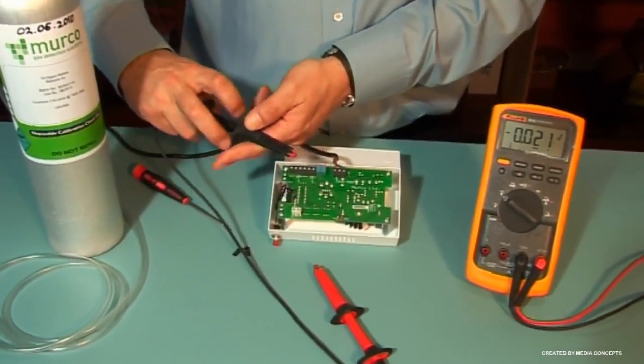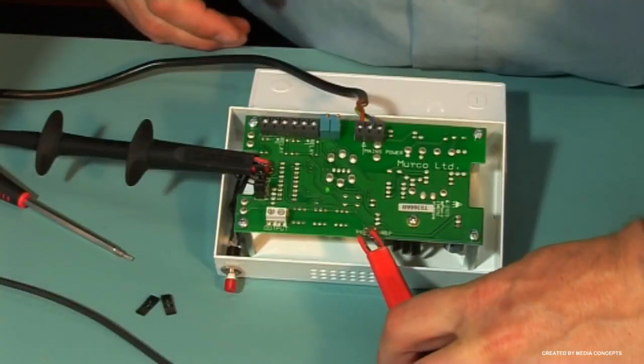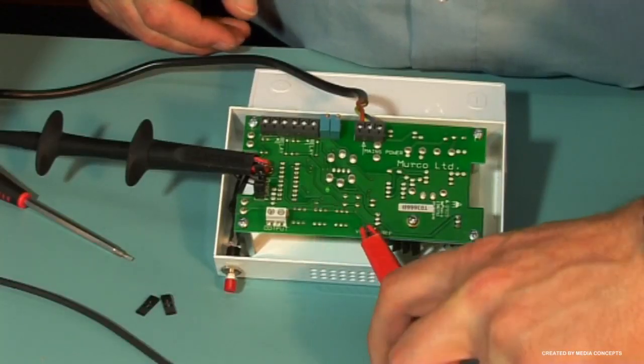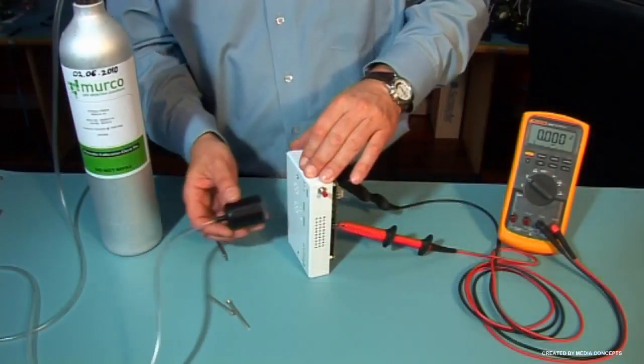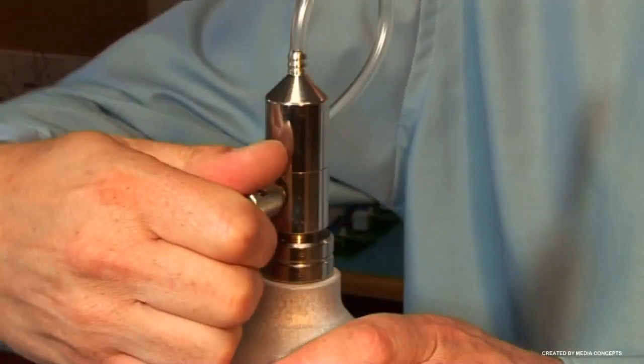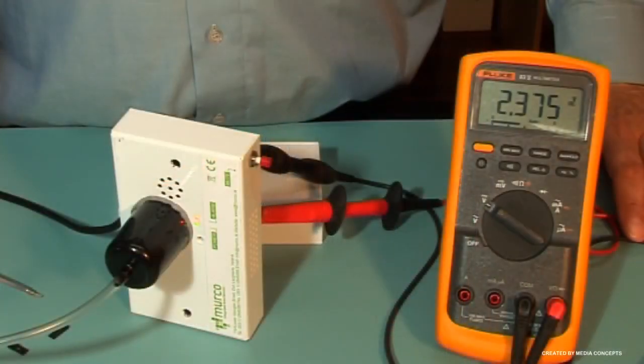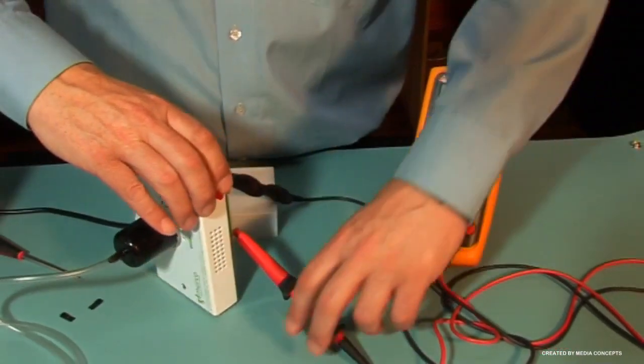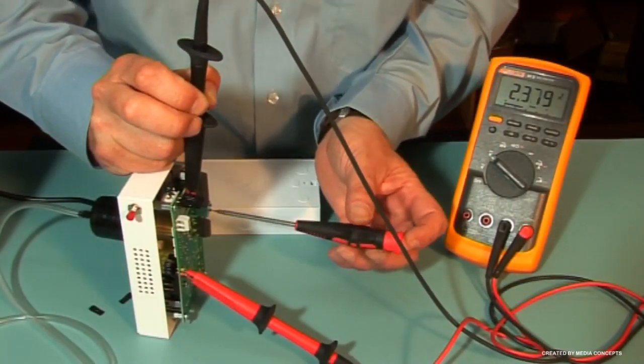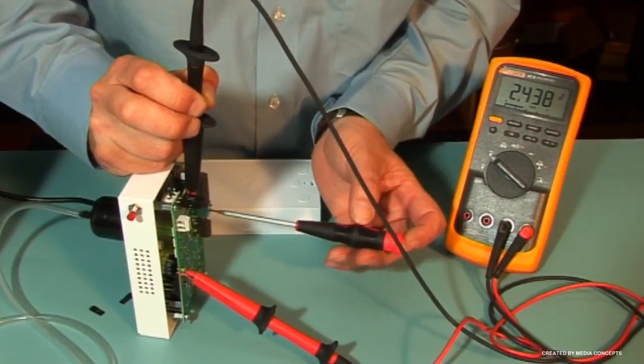Having carried out the electrical setup, connect the voltmeter between V0 and Vs with your known target gas and desired range, expose the sensor to the gas and allow the standby voltage to climb. Once the voltage stops climbing and stabilises, then that voltage is the alarm voltage and should be recorded. Record this value and then between V0 and Vref, adjust P2 to approximately 50 millivolts below this voltage.